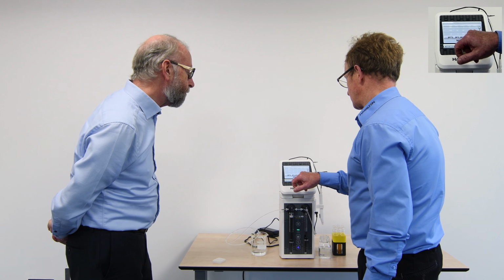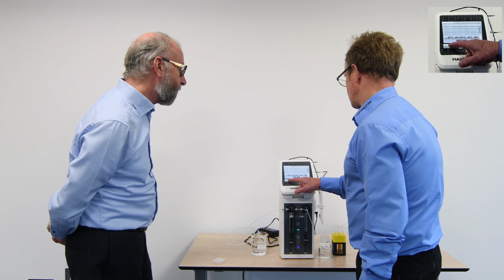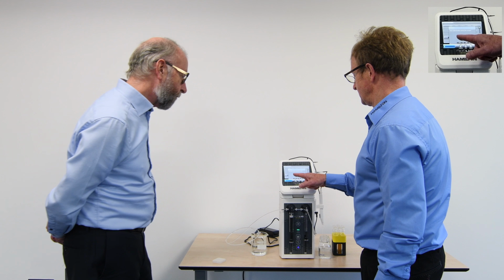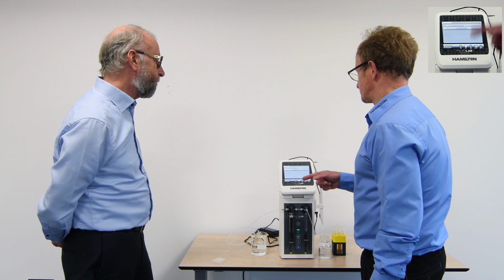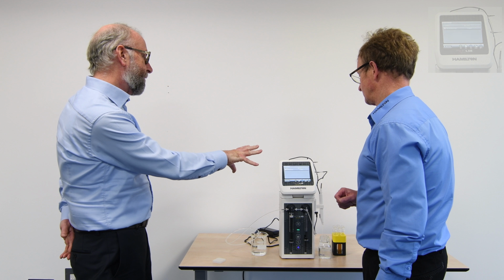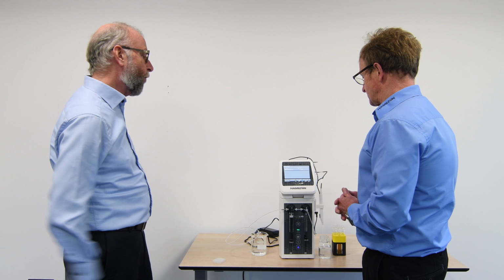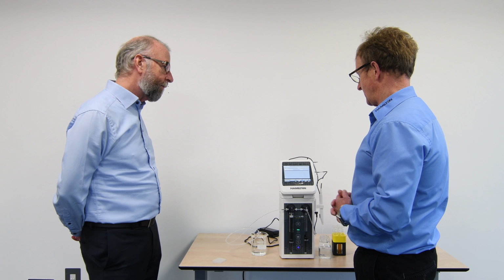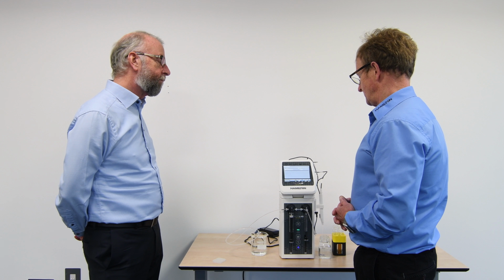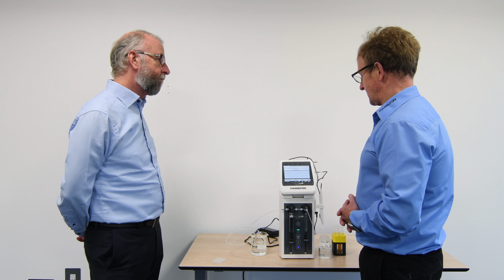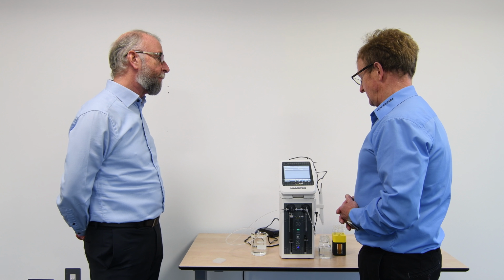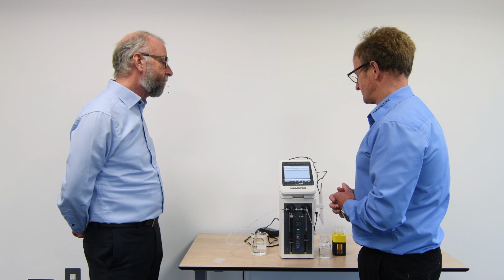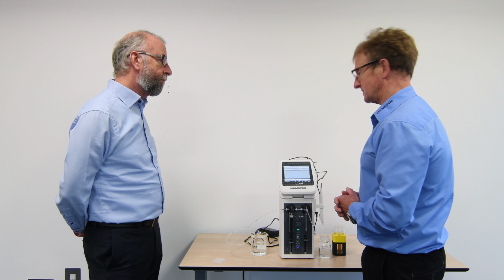But essentially now we've actually got that program in, we can come back out to custom methods, and it asks us, we're going to save before leaving the screen. Yep. I say yes, it's now stored that change of program. And this can be password protected. Exactly. All the methods can be password protected. The instrument is CFR 21 compliant. We have an administrator and a user mode. And the administrator can set up the programs which allow users to access the programs but not change them. So, and it has full traceability on the documentation it's generating.